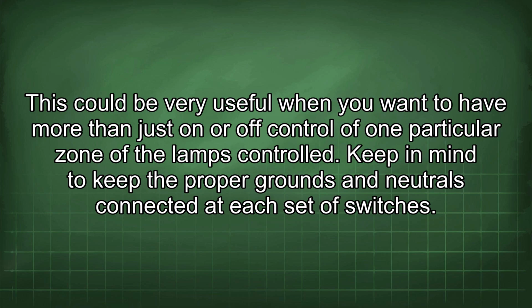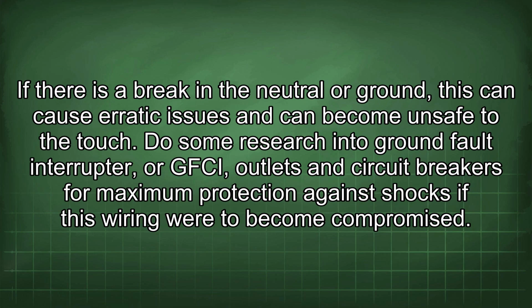Keep in mind to keep the proper grounds and neutrals connected at each set of switches. If there is a break in the neutral or ground, this can cause erratic issues and can become unsafe to the touch. Do some research into ground fault interrupter, or GFCI, outlets and circuit breakers for maximum protection against shocks if this wiring were to become compromised.